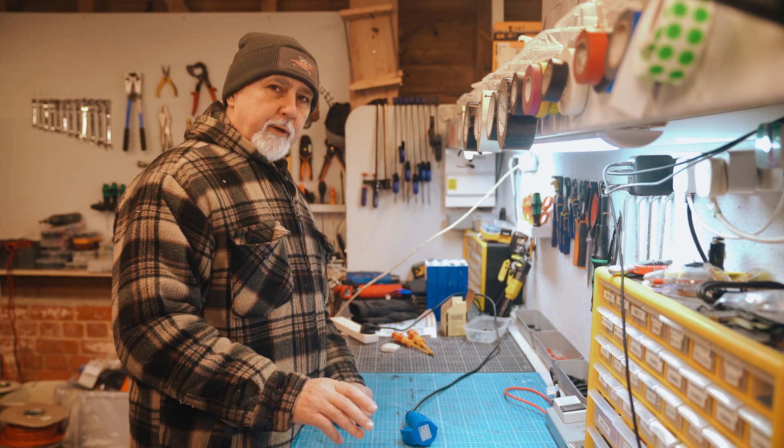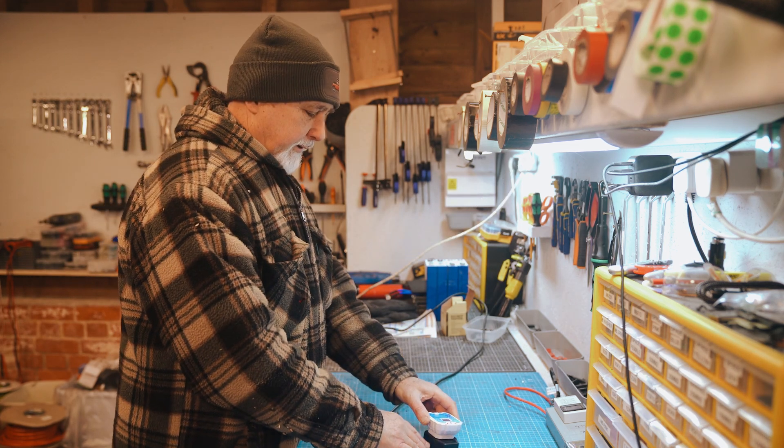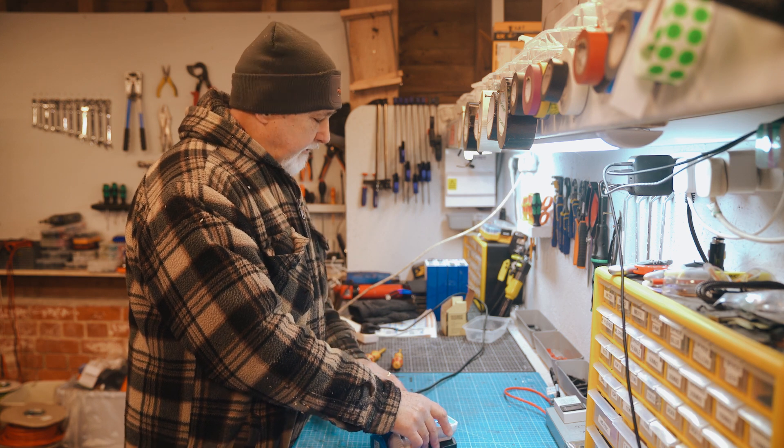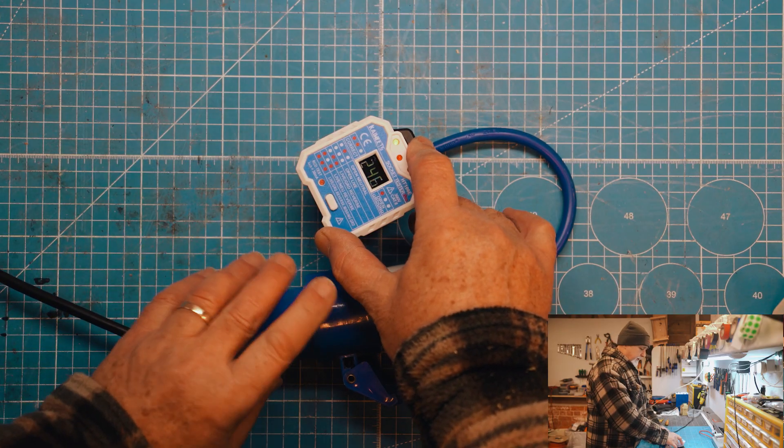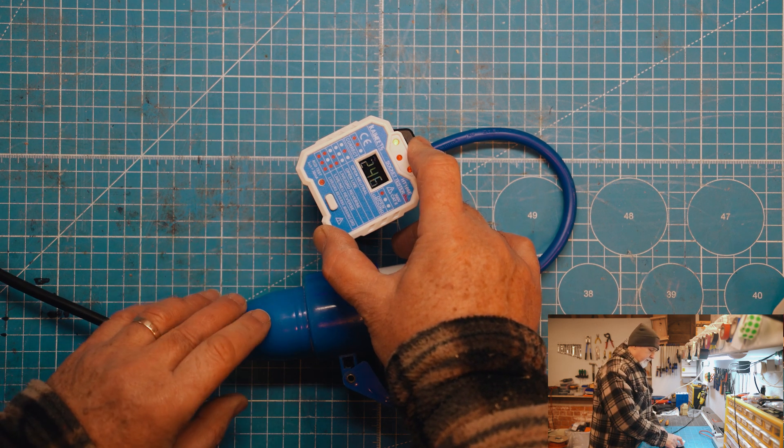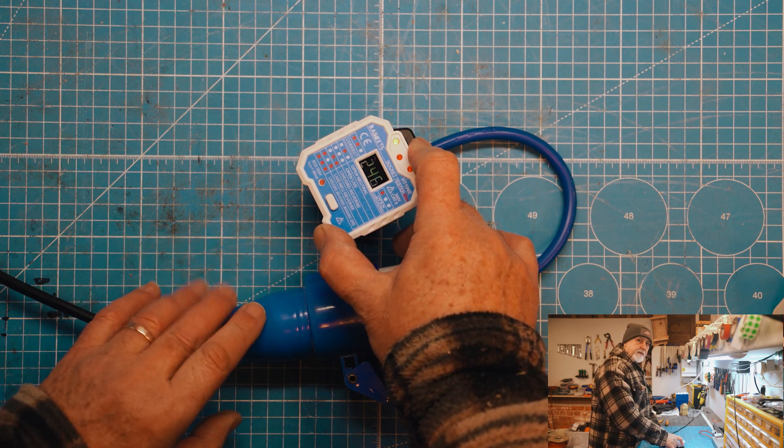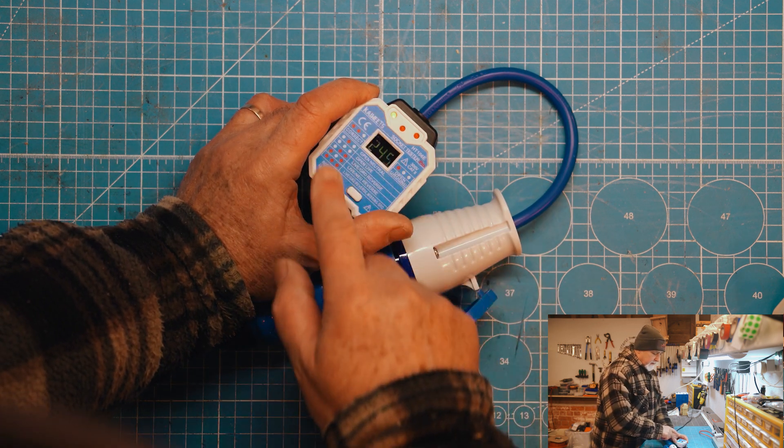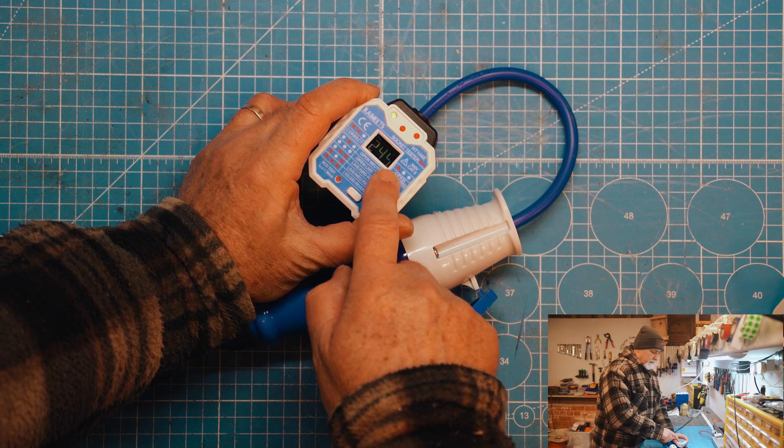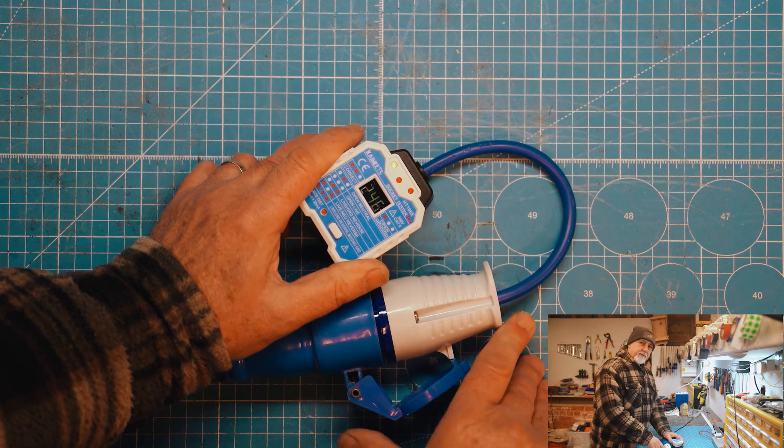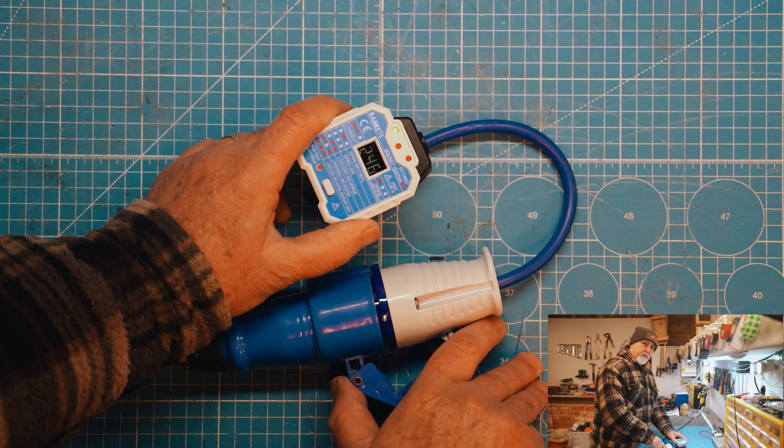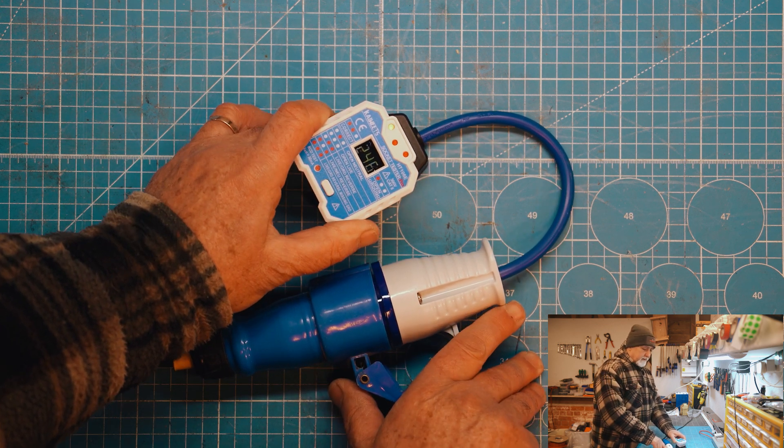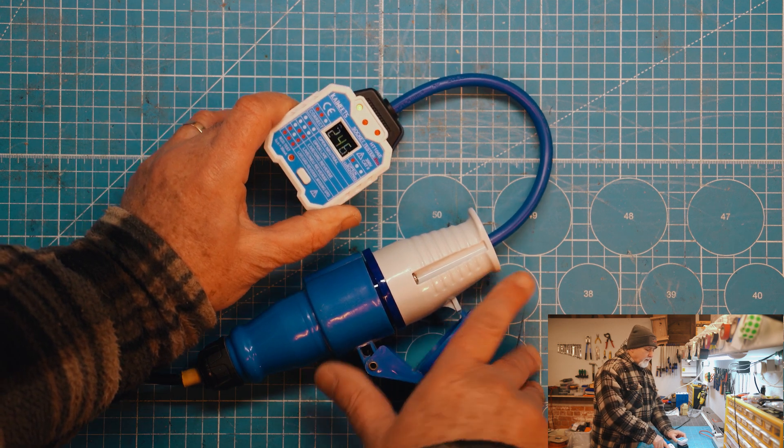Let's get on to the next demo. We're going to demo what it would look like if the earth is missing. So the last simulation, we have now, this is our campground with the earth removed. So your protection to all intents and purposes has been removed. If you look at this tester, one light showing that corresponds to open ground. So ground is missing. That's pretty serious really in that your protection, your RCD protection has been removed. And so there is the danger that that protection has been removed.